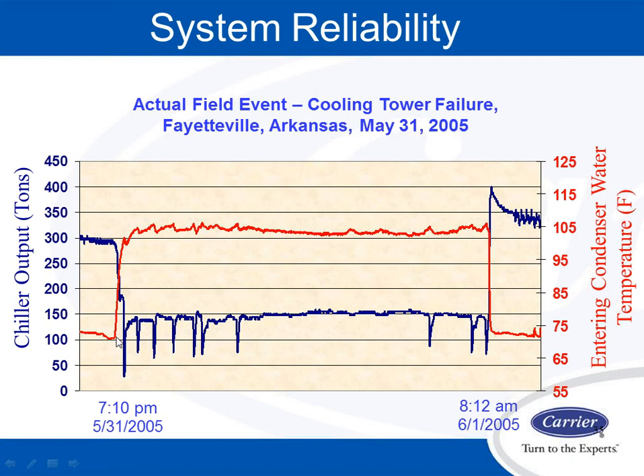Then a condenser water tower fan failed, and the condenser water temperature shot up to 105 degrees. When that happened, the chiller reacted, settled down, and operated at around 150 tons. It wasn't operating at 300 tons because the tower water was hot, but it was providing some cooling for the facility. After 12 hours, once it was repaired, the tons shot up, and it went back to operating at steady state 300 tons. There's not a machine in the marketplace that would do this. A centrifugal couldn't because it would surge. The screw compressor could because it will not surge. The refrigerant cannot flow backwards.